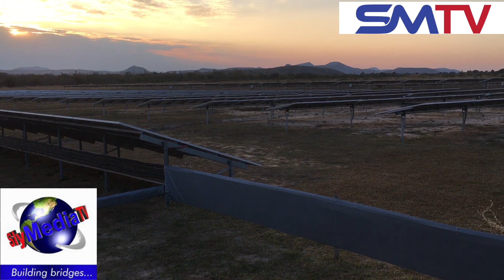We are generating power from solar. Our total capacity for this first phase is 2.5 megawatts. So we've got 9,600 solar panels here, connected 20 in series, which we call a string. For each inverter to generate, it needs 12 strings per inverter, which is 12 times 20 solar panels, equaling 240 solar panels per inverter. Each inverter generates from 1000 volts DC to 400 volts AC, 3-phase.